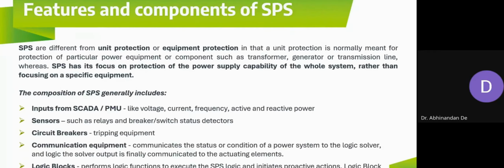Second come sensors. Sensors are needed to get the switch and breaker status and relay status, say whether the relay has operated or not, whether the breaker has opened or not, whether the breaker has closed or not. This is called breaker status, switch status, and relay status. So some sort of sensor should be there which will detect this switch status and transmit it. Then, of course, we need circuit breakers, because they are the main tripping equipment of the power system.